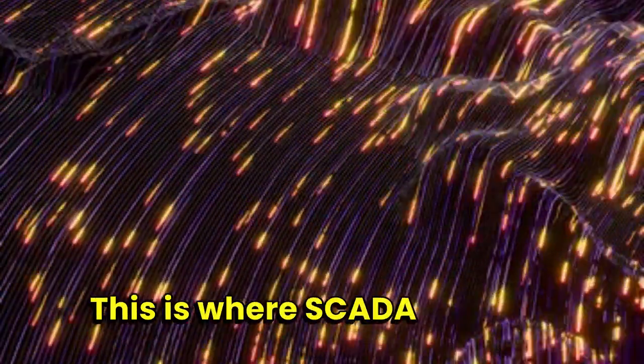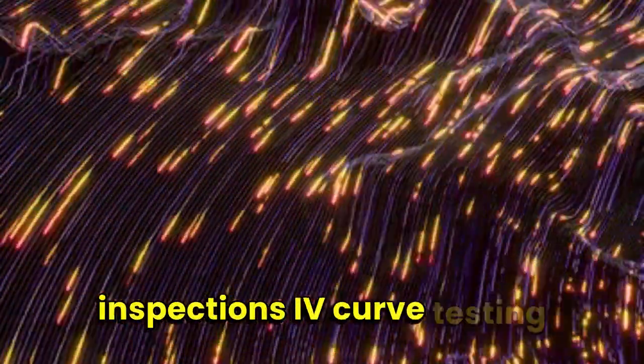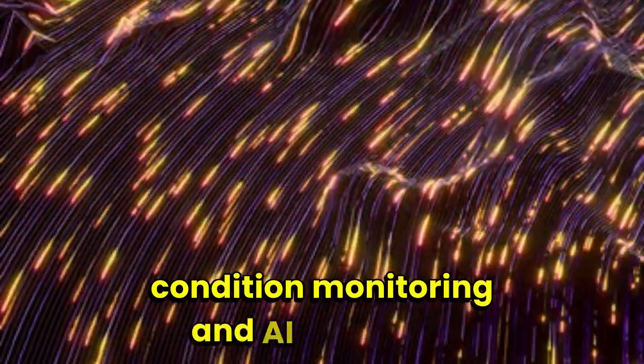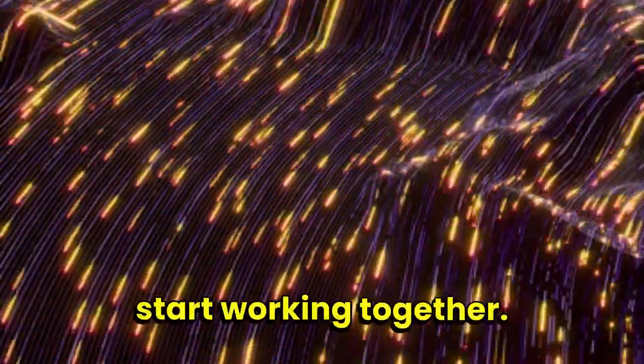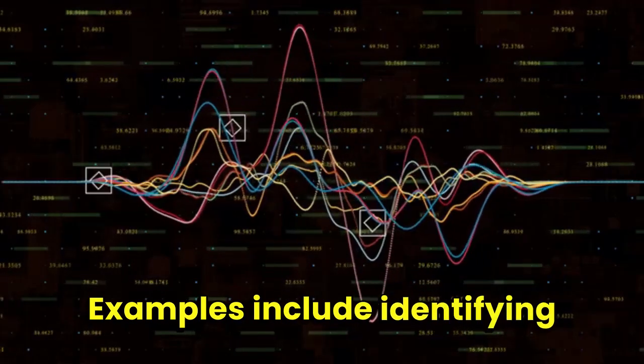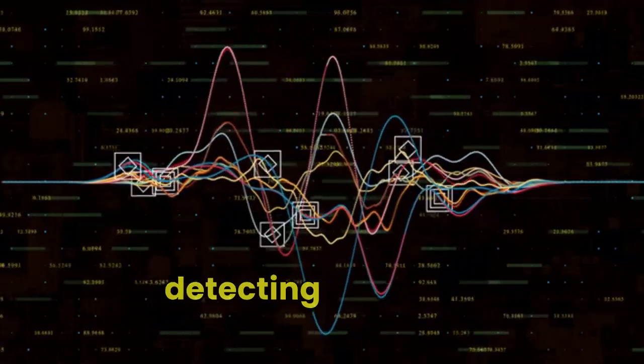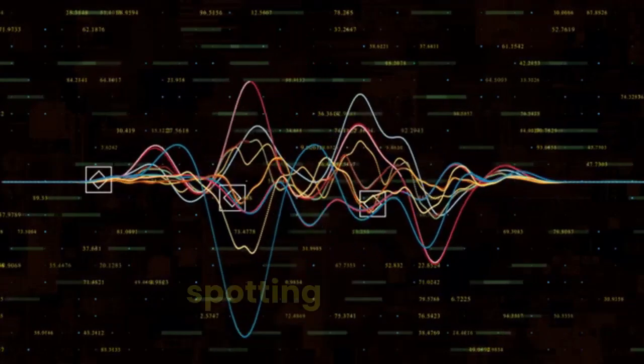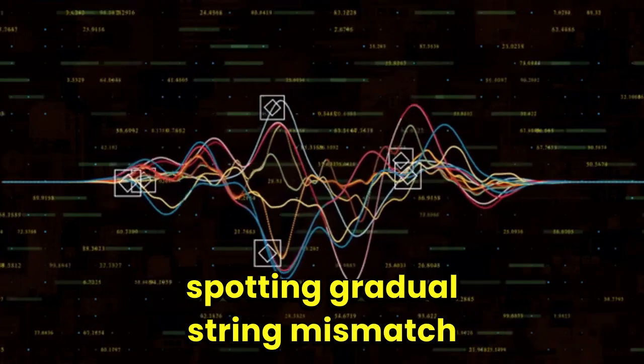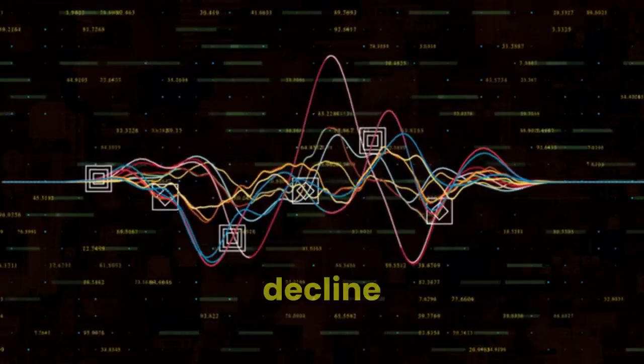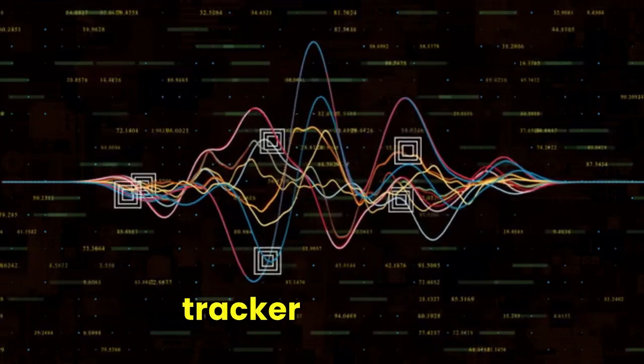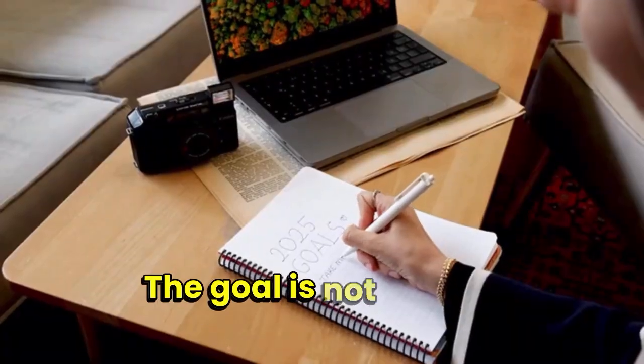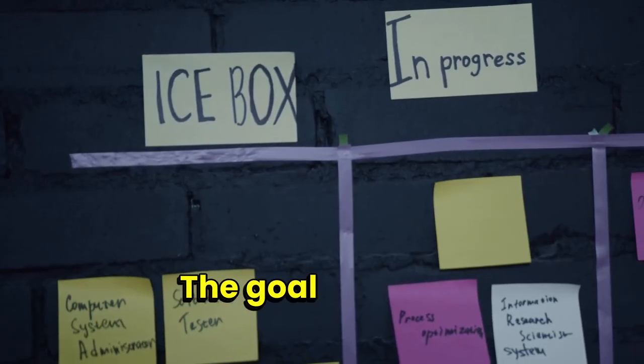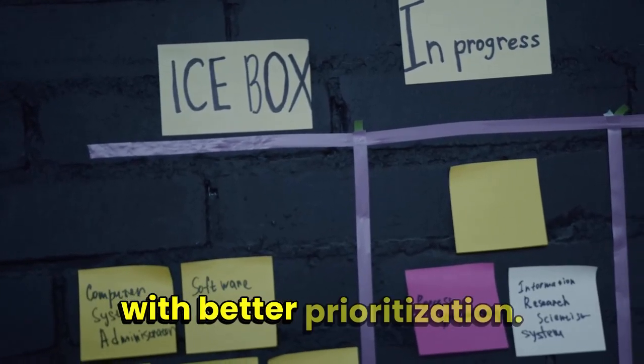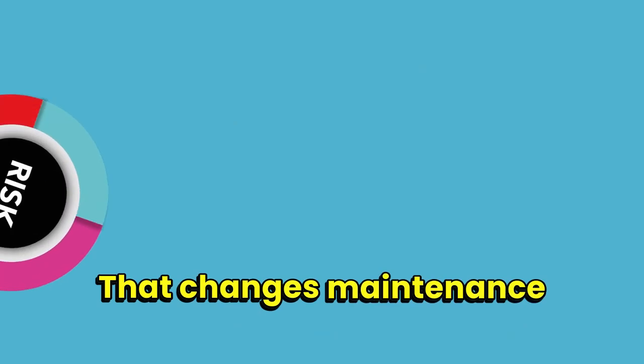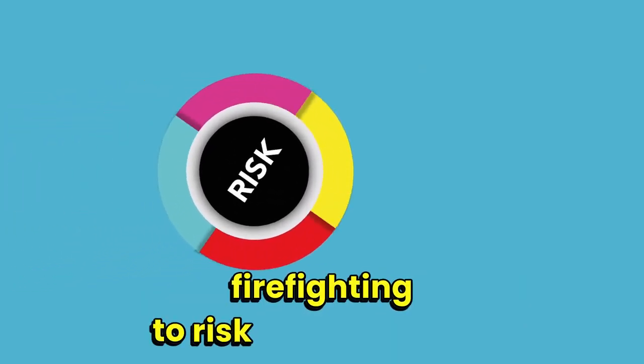This is where SCADA, thermal inspections, IV curve testing, condition monitoring, and AI analytics start working together. Examples include identifying rising inverter temperatures, detecting recurring clipping patterns, spotting gradual string mismatch, tracking insulation resistance decline, or identifying abnormal tracker behavior. The goal is not perfect prediction. The goal is earlier intervention with better prioritization. That changes maintenance from reactive firefighting to risk management.